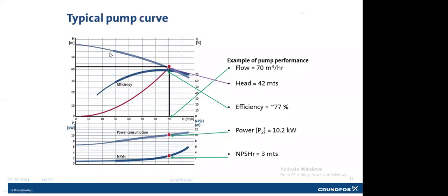There are four curves available. First is Q and H. This is the relation between flow and head. Here we can see as the head decreases, the flow increases, and vice versa, as head increases, the flow reduces. In most of the cases, what happens? The pump gets designed at a higher head. For example, if it is designed at 50 meter cube per hour at 50 meters head, and if the actual site head is 40 meters, it will operate at a higher flow, at 70 meter cube per hour.